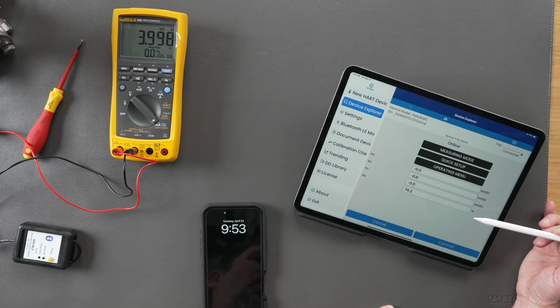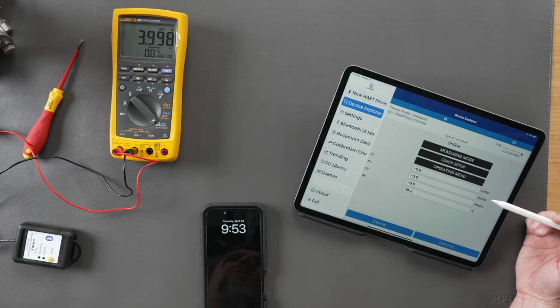So what we're going to do now is keep it really, really simple. What I see when I make that first connection is I'm getting all my HART variables: my PV, SV, TV, and typically I see that as a QV, but they've got it listed as a 4V. These HART variables can be changed. Most manufacturers allow you to go in there and program whatever you want. Not a huge deal in this scenario, but if you had a multi-variable device that we were trying to pull multiple parameters off of, we could pull that via HART, okay?